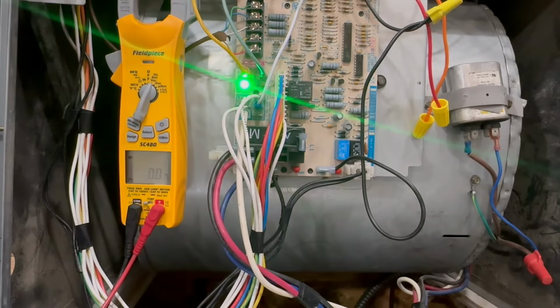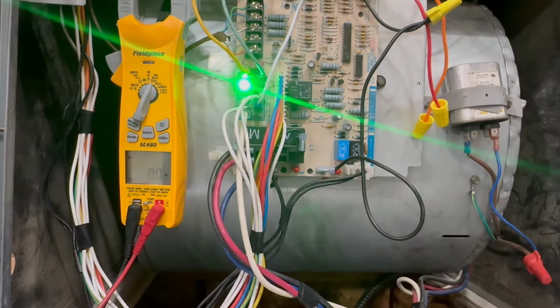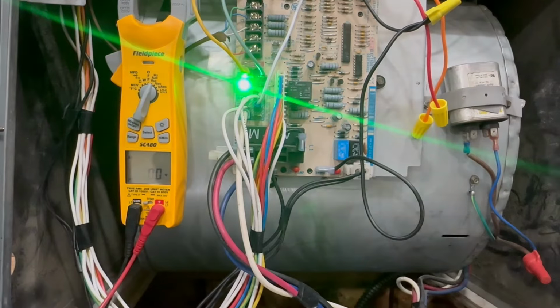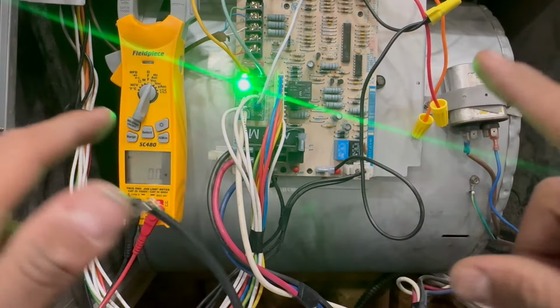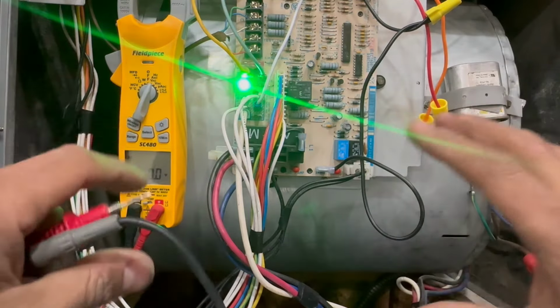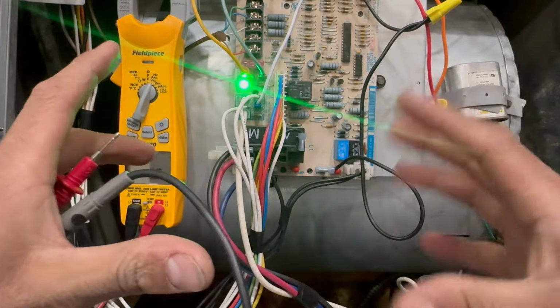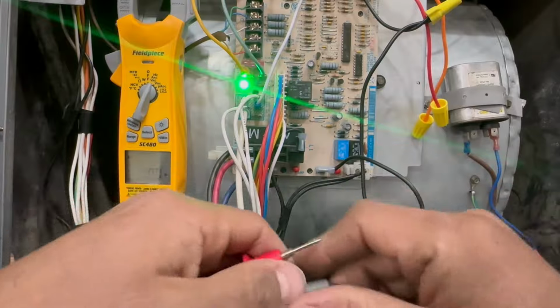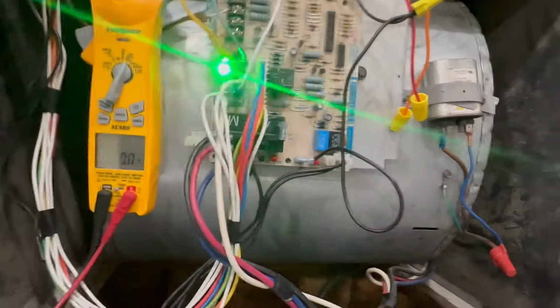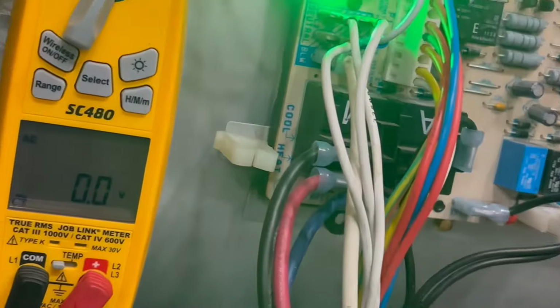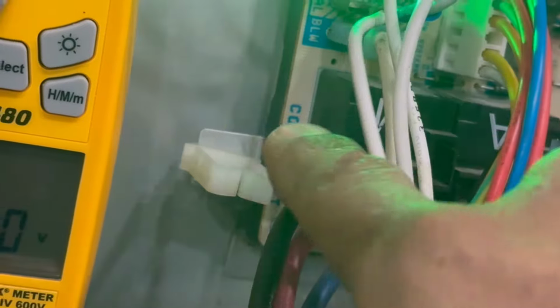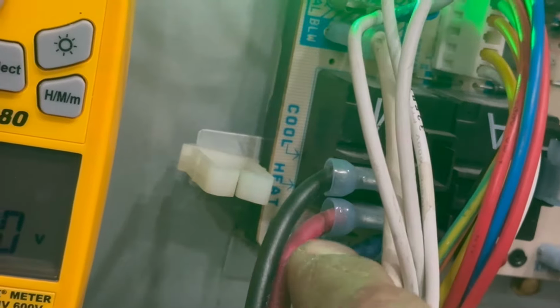Okay, we're finally in the last step here, which is B, and the FB, which is your blower motor. So you're going to see that it's going to do all the steps, but it's not going to turn on the blower motor right away. It's actually waiting for that heat exchanger, that chamber, that area to get hot. Because if it turns on right away, you're going to supply cold air to the customer. So right here, you see right there, it says cool, and it has heat. So it has a PSC motor.